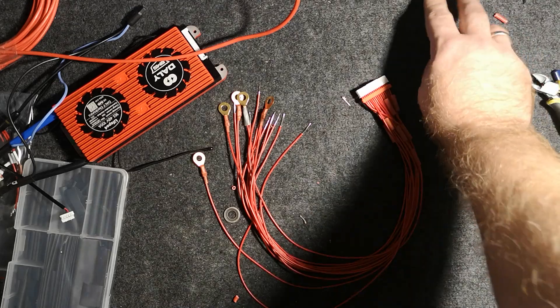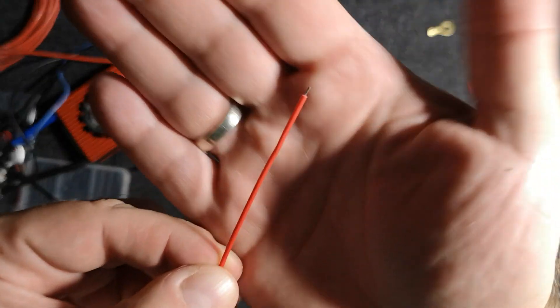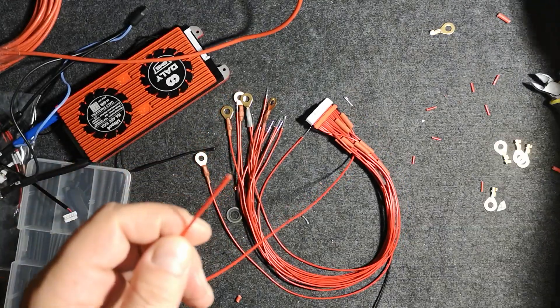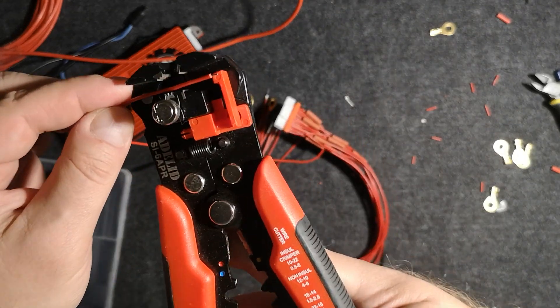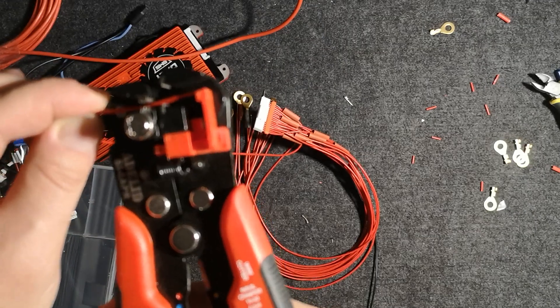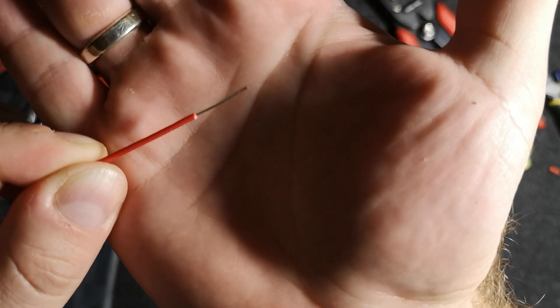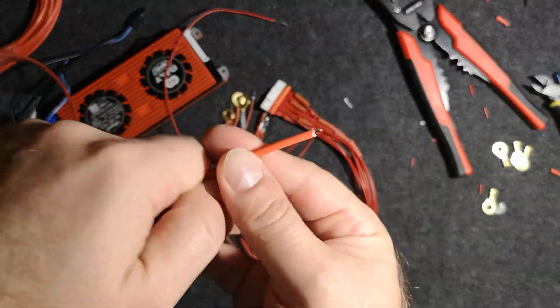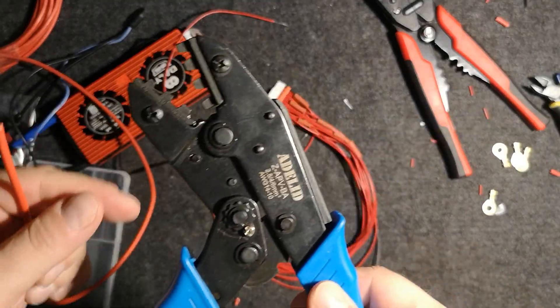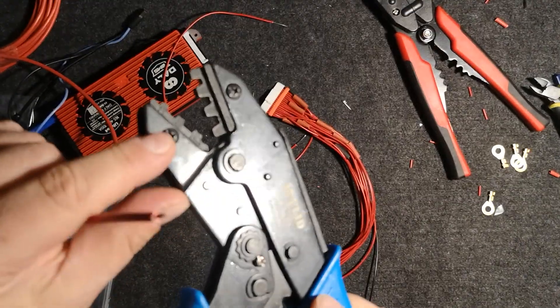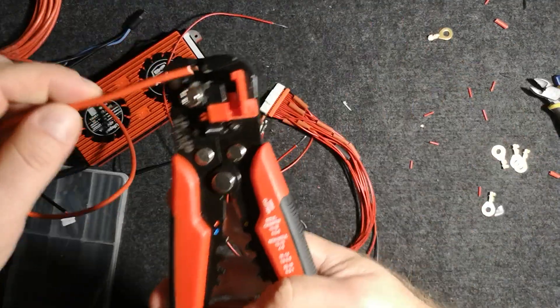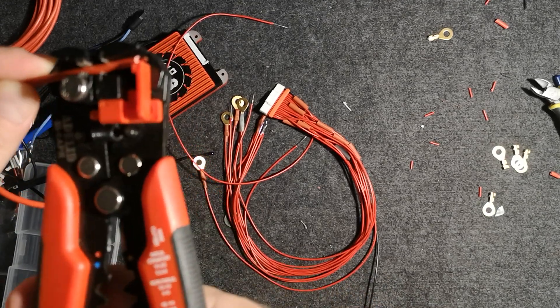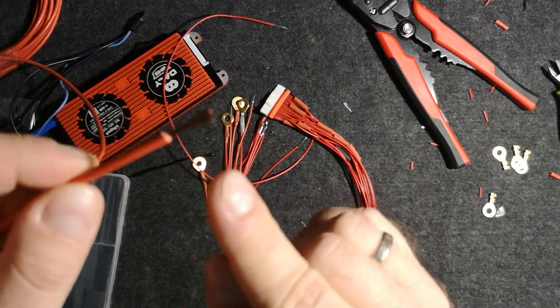So in my case it is 2.5 millimeters square. This is how this cable looks like. I will try to show you everything in short. This is my insulation remover. There's another video on my channel where I'm showing how to use it. Basically I will remove about one centimeter, 10 millimeters of the insulation. I will wrap this on this cable and crimp it using universal crimping pliers. It could be used for solar MC4 connection but also it is for 2.5 as you can see. What I'm doing: take this and also remove about one centimeter insulation, something like this. If more, don't worry. If less, it could be problem.